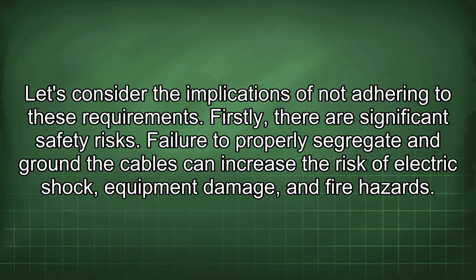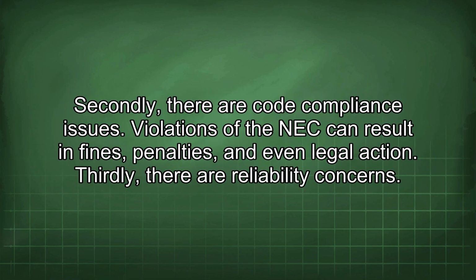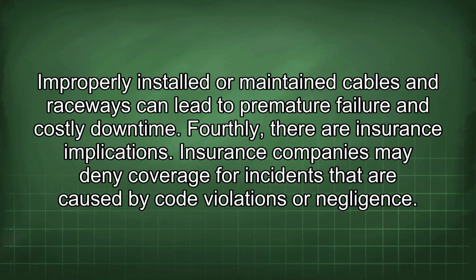Let's consider the implications of not adhering to these requirements. Firstly, there are significant safety risks. Failure to properly segregate and ground the cables can increase the risk of electric shock, equipment damage, and fire hazards. Secondly, there are code compliance issues. Violations of the NEC can result in fines, penalties, and even legal action. Thirdly, there are reliability concerns. Improperly installed or maintained cables and raceways can lead to premature failure and costly downtime.